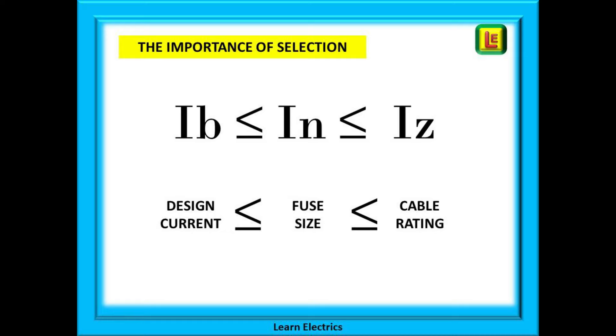The equation tells us that IB must be equal to or less than IN, and that IN must be equal to or less than IZ. You can see below the equation just what these symbols mean. The design current — that is to say what the appliance is manufactured to take — must be equal to or less than the size of the circuit breaker. If not, the breaker would trip every time the appliance was switched on.